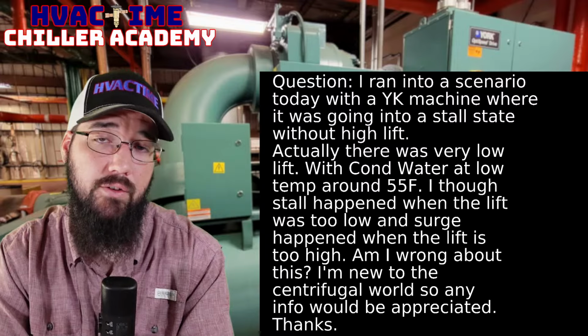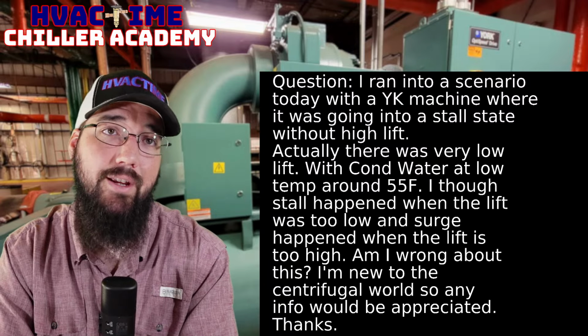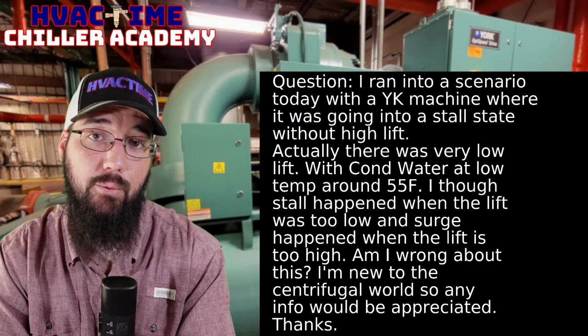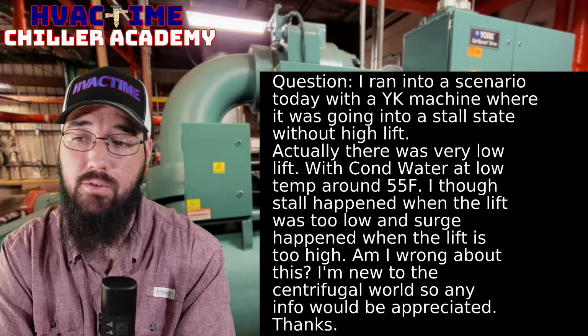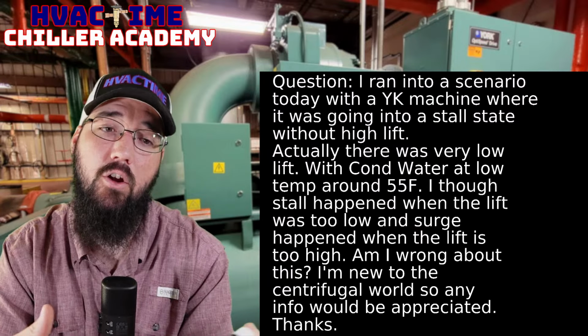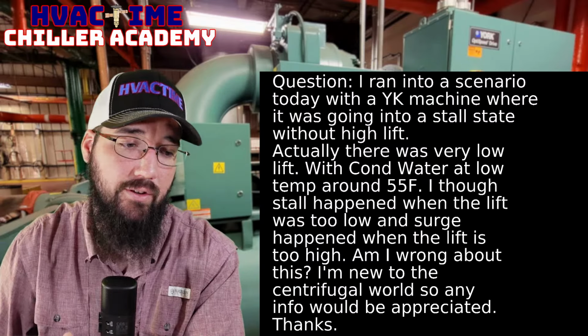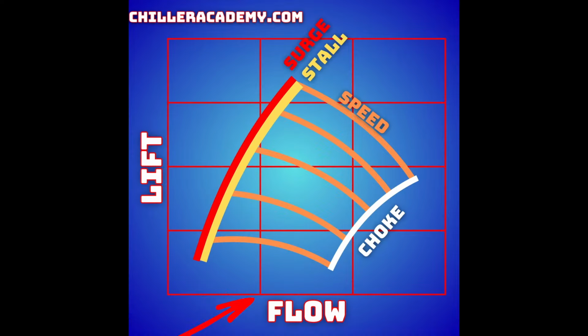And under those conditions, with a really good load, we could handle really high lifts. So you could run some significant lifts across a centrifugal as long as it has enough load input into it. And you can see that on the graph as flow increases. So if we come over here where we've got high flow, we can run some pretty high lift, right? And this graph, mind you, is not perfect. It's just representative, but this is similar to what a surge graph will look like for a centrifugal. Now, you can still push up into a surge here, all right? Just bear that in mind. But the point is, with high load, you can manage high lift.